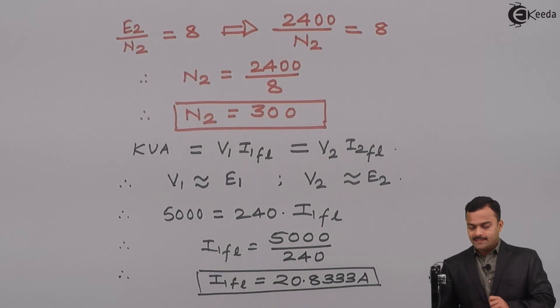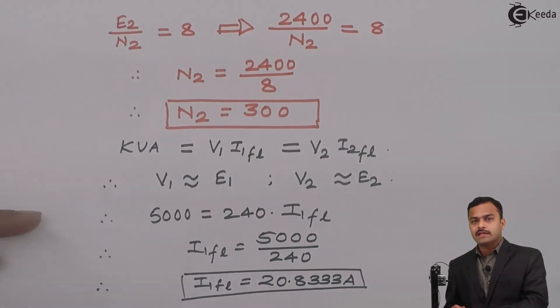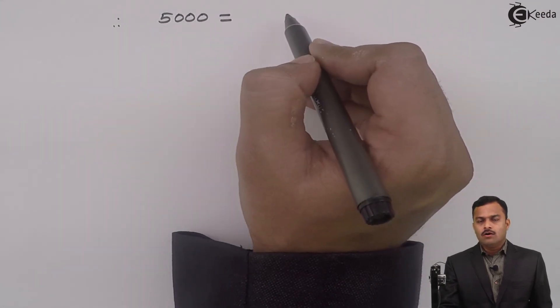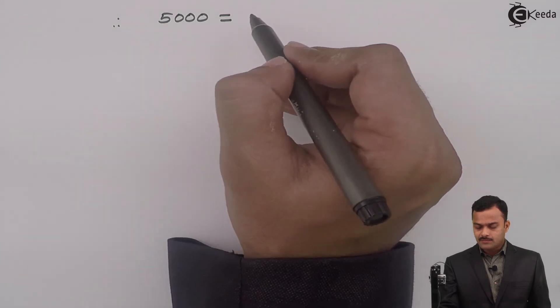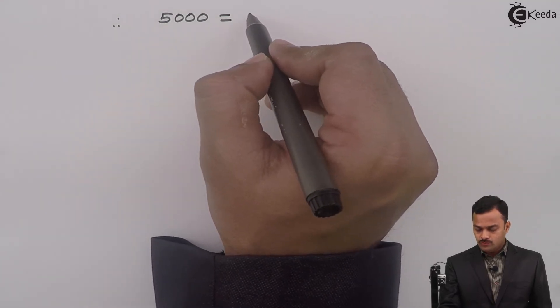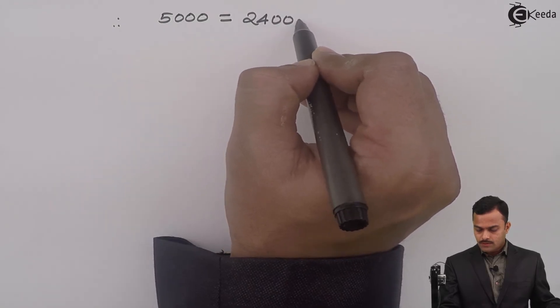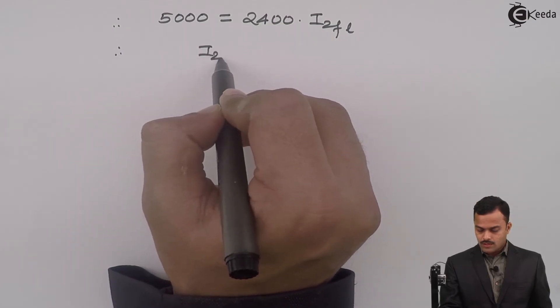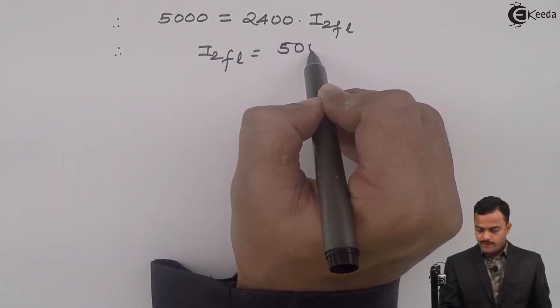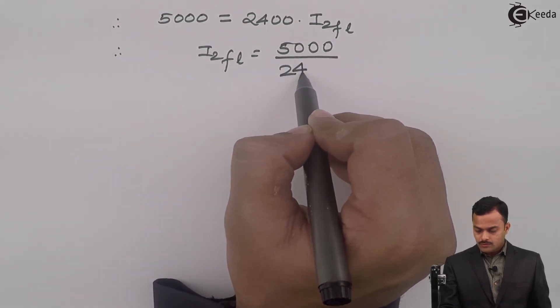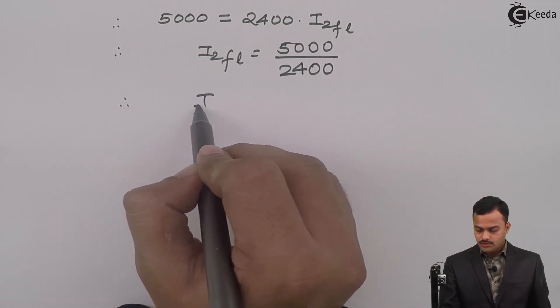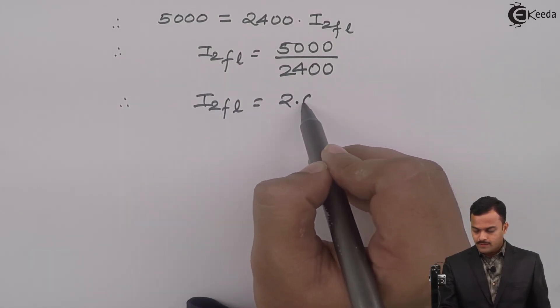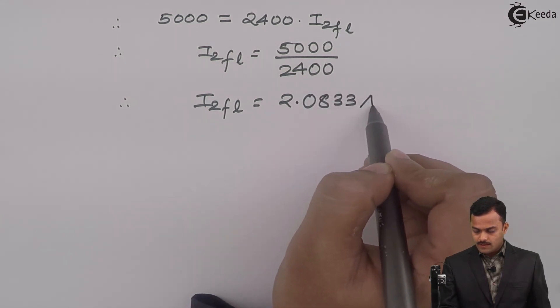Similarly, I can get I2 FL. So, for I2 FL I will use E2. 5 kVA or you can say 5000 VA equal to E2 that is 2400 multiplied by I2 FL. So, I2 FL equal to 5000 divided by 2400. Solution will be I2 FL which is 2.0833 ampere.